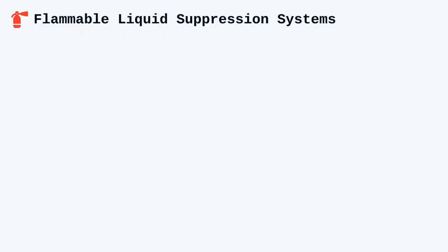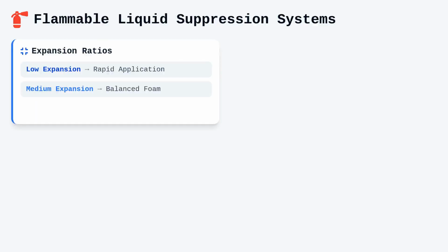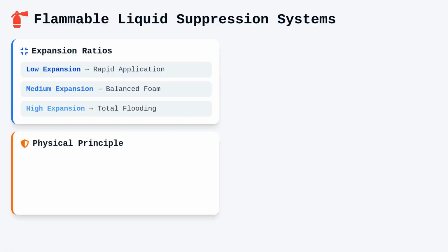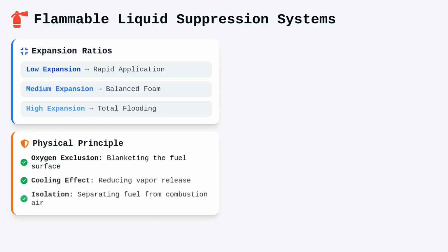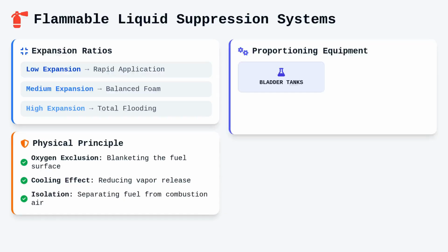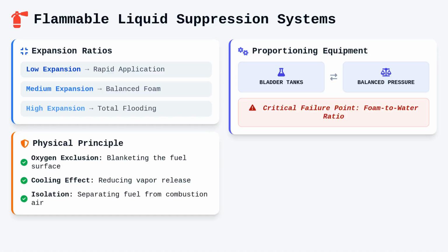When addressing flammable liquid hazards, we shift our focus to foam suppression systems, which are classified by their expansion ratios into low, medium, and high application categories. The physical principle here involves blanketing the fuel surface to exclude oxygen and provide a cooling effect that prevents the release of flammable vapors. Proportioning equipment, such as bladder tanks or balanced pressure proportioners, must maintain a consistent foam-to-water ratio across varying flow demands, which is a common point of failure in field audits.